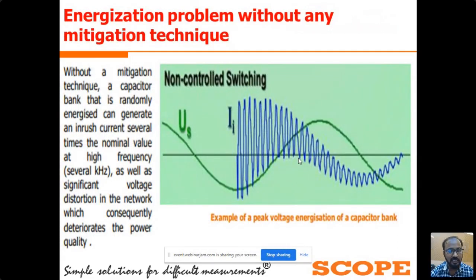As we have seen for the shunt reactor application, the capacitor bank is also an example of a capacitive load, and we know that a capacitive load opposes the sudden change in system voltage. So in the waveform, you can see that if we try to close the capacitor bank near to the voltage peak, it will create the maximum disturbances in our system. So for the capacitor bank, we try to close it near to the voltage 0.